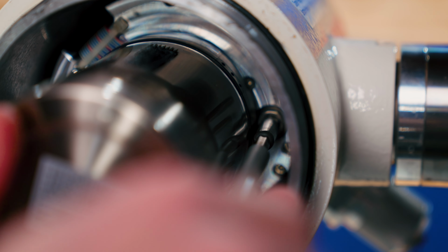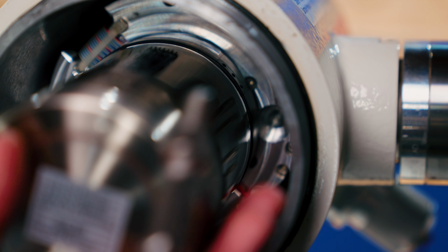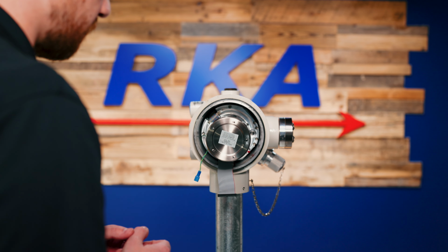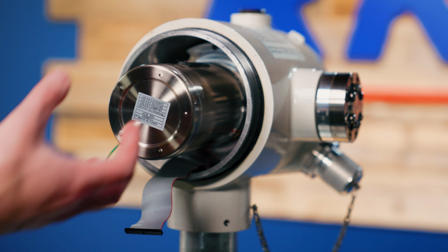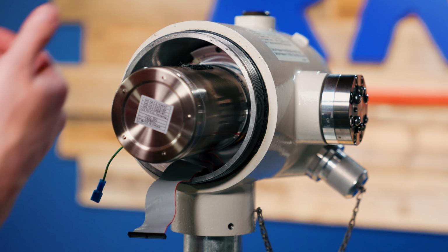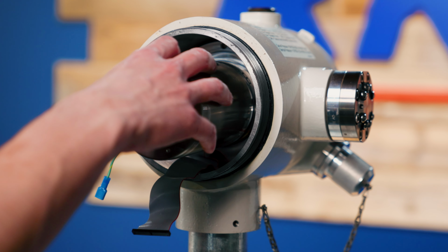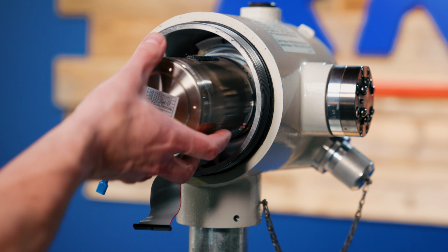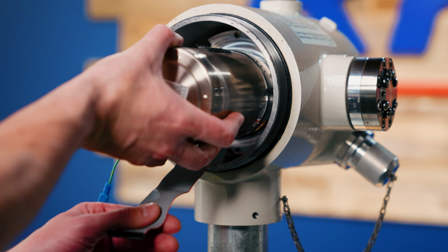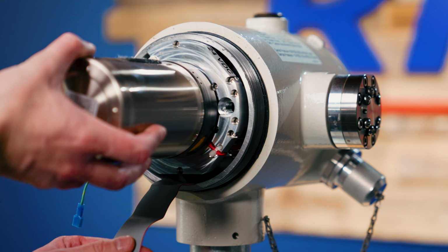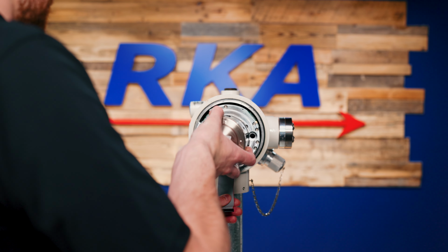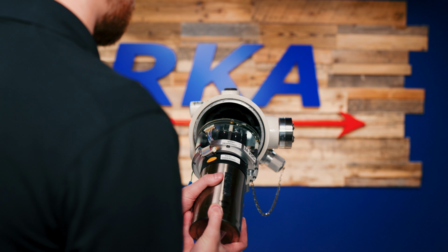You can loosen the hex bolt and remove it. Now that the GC module can be removed, we can go ahead and remove it from the housing, but we do have to remove two cables from the back of it first, so you do not want to pull it all the way out or yank out the module. So now, keeping in mind, again, the ribbon cable, not pulling on it too hard and not pinching it or crimping it, we can expose the back of the module.